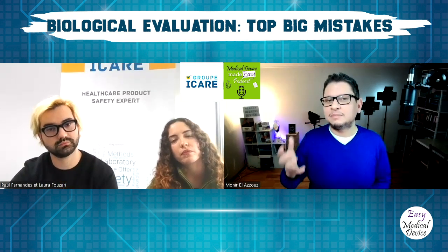But so, for example, let's say a software doesn't need a biological evaluation. It's not touching the patient, but there is still a biological assessment to be done for a software. For a software, it's an exception, of course. The software will not touch the patient, but if you follow the MDR, the MDR tells you that you have to ensure the biological safety of your product if it's a medical device.